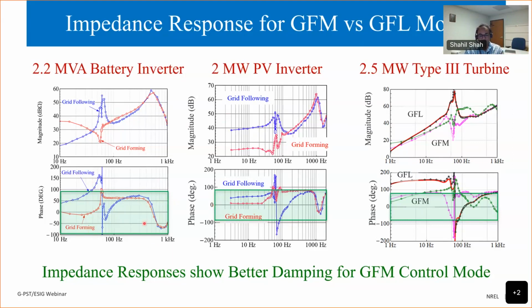One interesting thing that we found during all this measurement is that most grid forming devices, whether a battery inverter, PV inverter, or wind turbine, have a better damping characteristic. Their phase of impedance stays closer to 0 degrees, or basically they stay positive, behaving like a positive resistance at those frequencies, which reduces the risk of control interactions, which you can see in this 2.2 MVA battery inverter or 2 megawatt PV inverter. But the response was really striking with the type 3 wind turbine. Instead of the huge negative resistance that we see in grid following mode, the grid forming mode had a really low, positive resistance. So what we figured out is that type 3 wind turbines are less likely to suffer SSR in grid forming mode, which they are prone to suffer if we operate them in grid following mode.